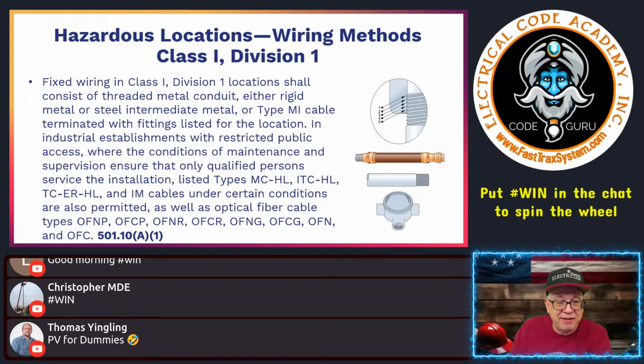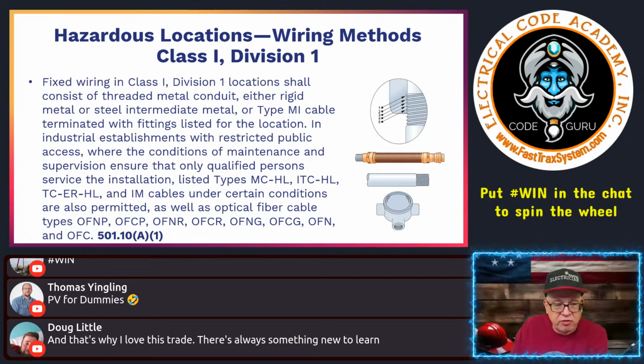Not PV for dummies, that's right, buy that book and learn on the job. You have to remember that an MC cable typically is not normal interlocked MC, it's usually a corrugated style. So MCHL is MC metal clad for hazardous locations. It's a little different.